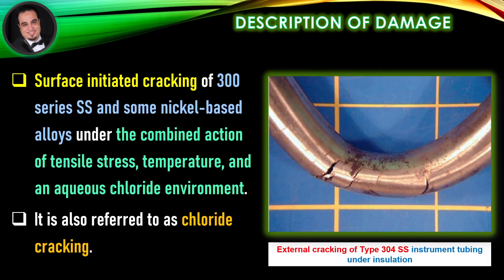Description of damage: Surface initiated cracking of 300 series stainless steel and some nickel-based alloys under the combined action of tensile stress, temperature, and an aqueous chloride environment. It is also referred to as chloride cracking, as illustrated in the figure.